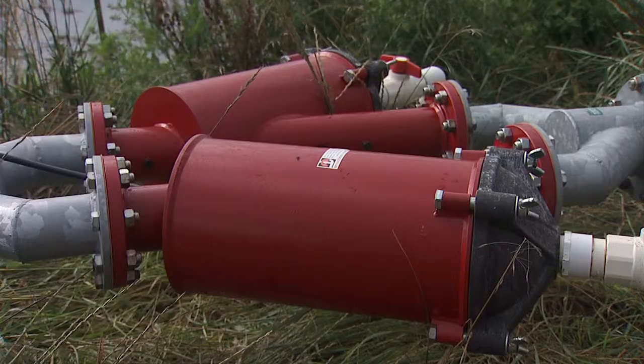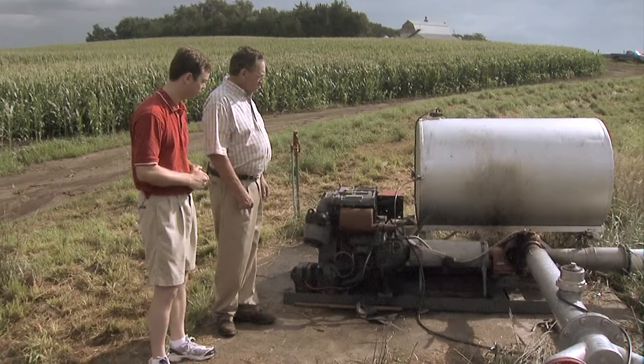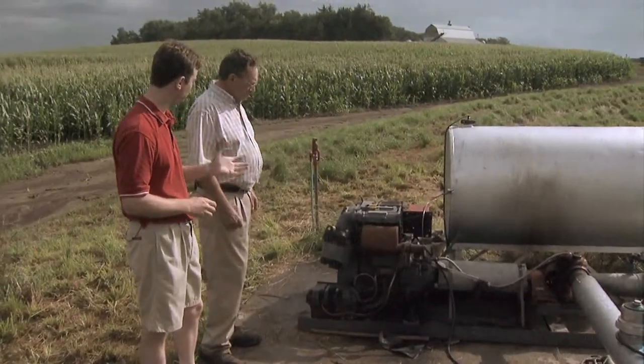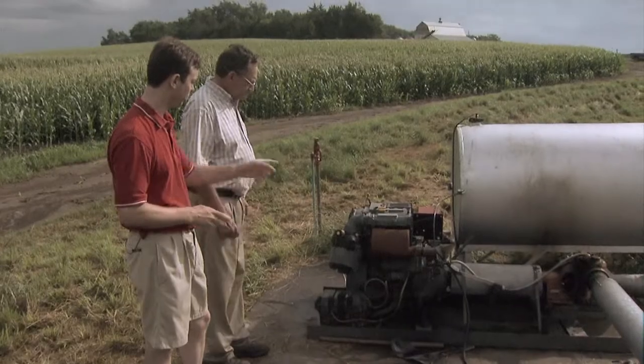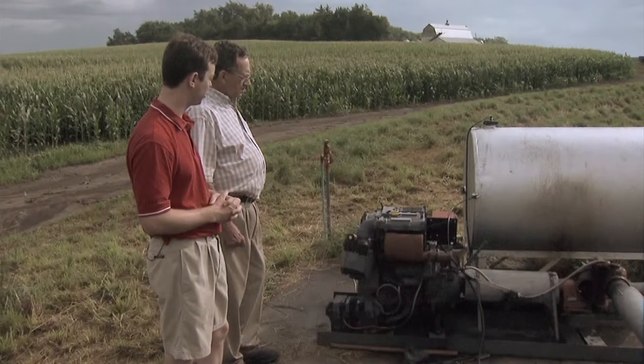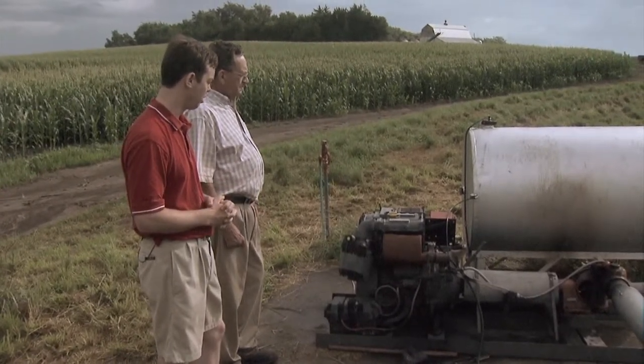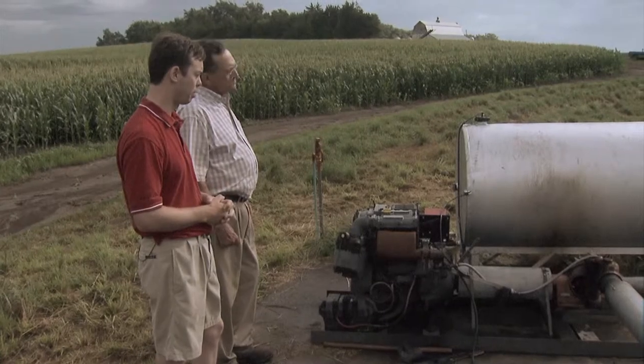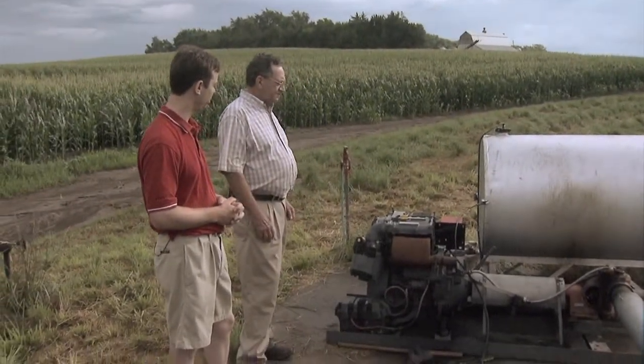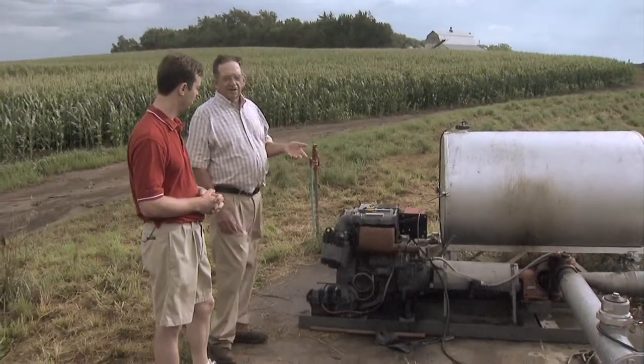They're really effective. We've got air-vac relief too. The pump is a 30-horse air-cooled Deutz with an exhaust primer and a full set of Murphys. We use diesel fuel because diesel doesn't go stale on us like gasoline, so it's always ready to go. How long does it take to start this pump up? Most times you've got it running, vacuumed, and actually pumping within five minutes.